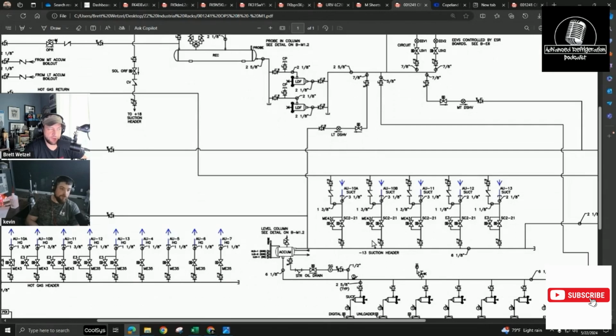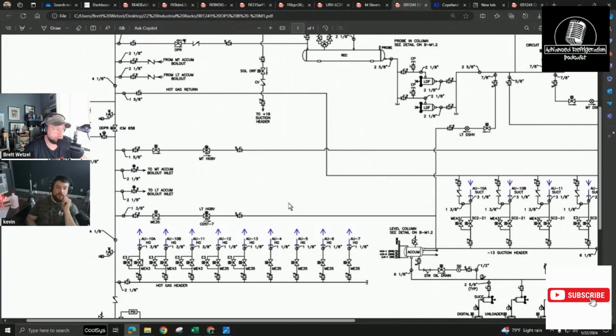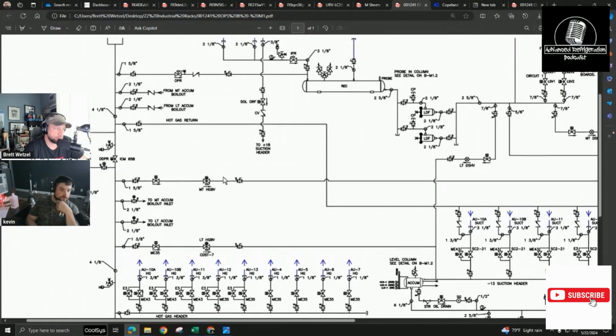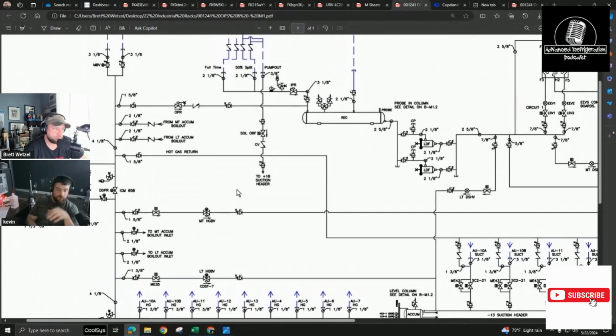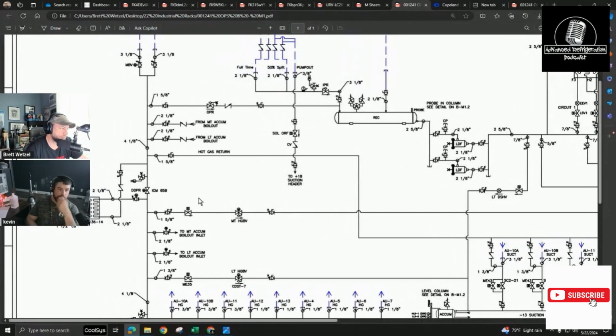Yeah, I saw one when we talked about it on the CO2 racks, where you're like, no, they usually don't do liquid injection. And then I didn't see it, and then I saw another couple racks after where they're really starting to do it. Even on their DX racks, they're adding it. Yeah, like their HFO and HFC racks, they're adding liquid injection and hot gas, and then they have accumulator heaters on them to prevent the flood back.